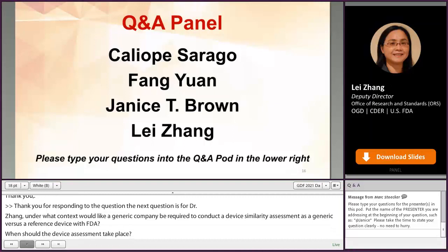Thank you for that question. I'll try to keep my answer brief because this session does not really talk about it. FDA has a separate guidance on comparative analysis and related comparative use human factors studies for a drug-device combination product intended to be submitted under an ANDA. The guidance lays out very nicely the process and the threshold analysis that FDA will conduct, and industry can use that to determine what level of study may be needed depending on their device versus the RLD device.